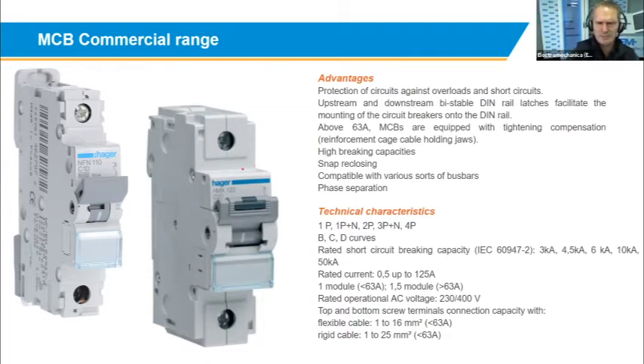And as I explained to you with the miniature circuit breaker, the lockout mechanism on the product, some of the bigger products, the 80 to 125 amp, actually have this black, what do you call it, pull-out mechanism on the toggle. So if you actually pull this out, that is also a lockout mechanism, and you can put a small cable tie or something through it, just to ensure that nobody switches this product on or off, which is a nice feature. So you don't need to have a special clip going around to do the lockout of the product.